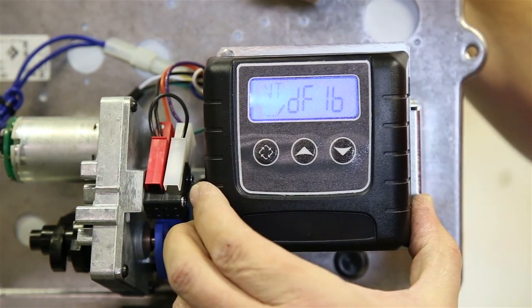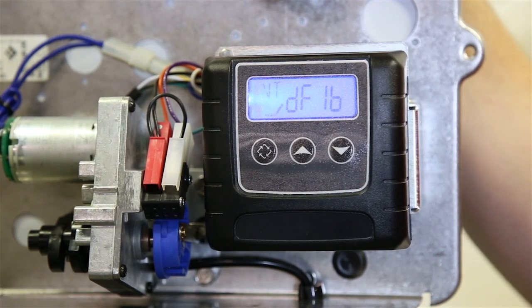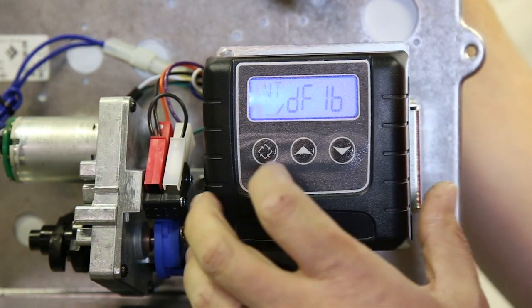Now that we're at 12:01 PM, we can enter the master programming mode and to do that, we hold the up and the down arrow at the same time for three to five seconds and you'll see the screen change to DF and then GAL. Now this stands for display format and it's in gallon, so we want to leave that there. So we're going to push this save or enter button again and it's going to take us to the next parameter. Now this parameter is called valve type and we want this set on downflow, one backwash. We want to leave that on downflow, one backwash.